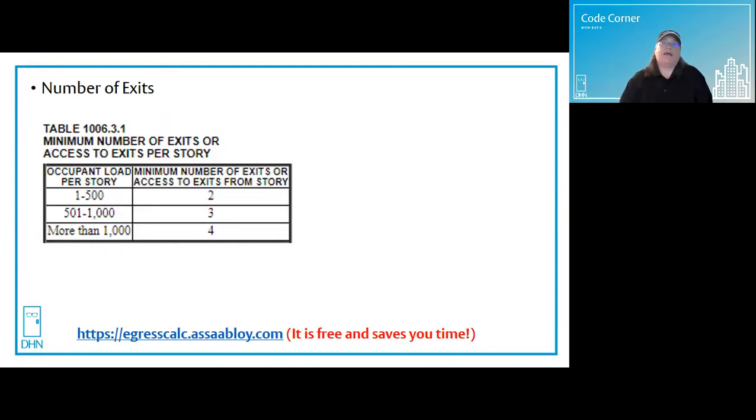The minimum number of exits or exit access per story or space with an occupant load of one to 500 people is two minimum. 501 to 1,000, you need three, and more than 1,000, you're required to have a minimum of four exits.